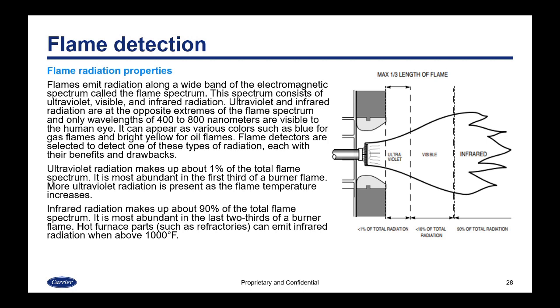Flame detectors are selected to detect one of these types of radiation, and each will have benefits or drawbacks. Ultraviolet radiation makes up only about one percent of the total flame spectrum and is most abundant in the first third of a burner flame. More ultraviolet radiation is present as the flame temperature increases. Infrared radiation makes up about 90 percent of the total flame spectrum and is most abundant in the last two-thirds of a burner flame. Hot furnace parts such as refractories will begin emitting infrared radiation when above 1,000 degrees Fahrenheit.